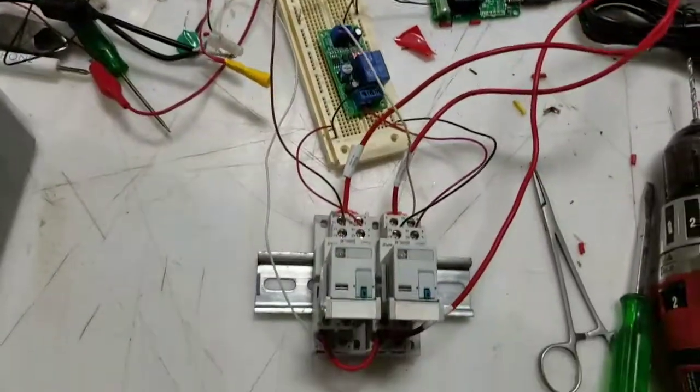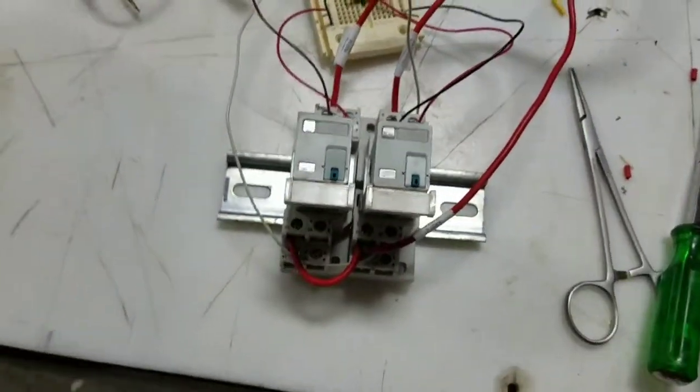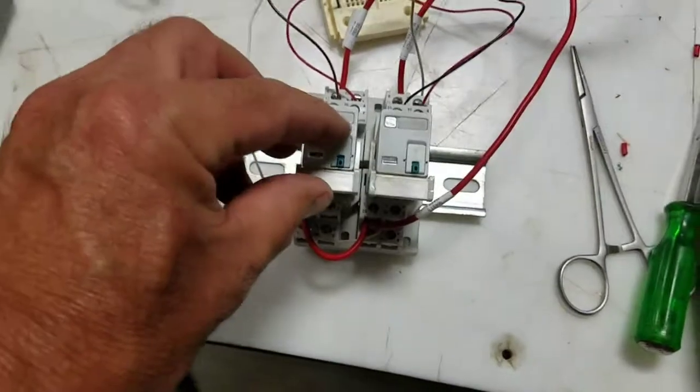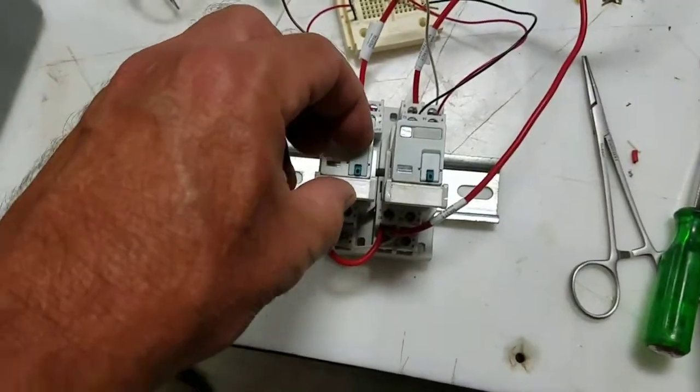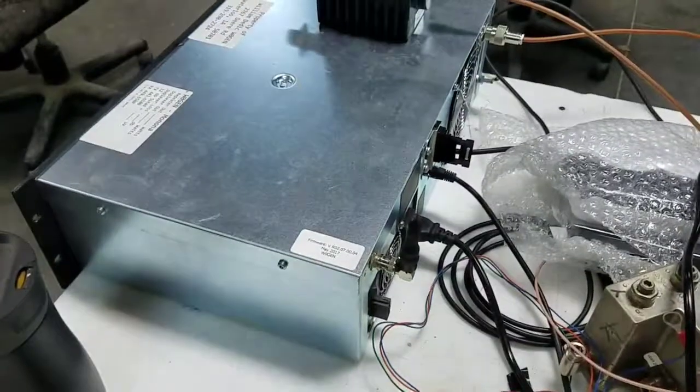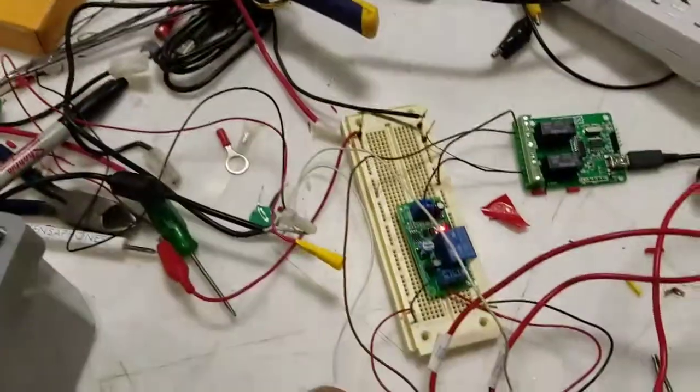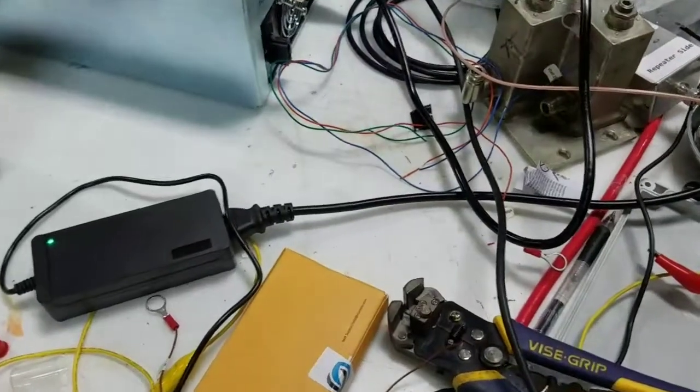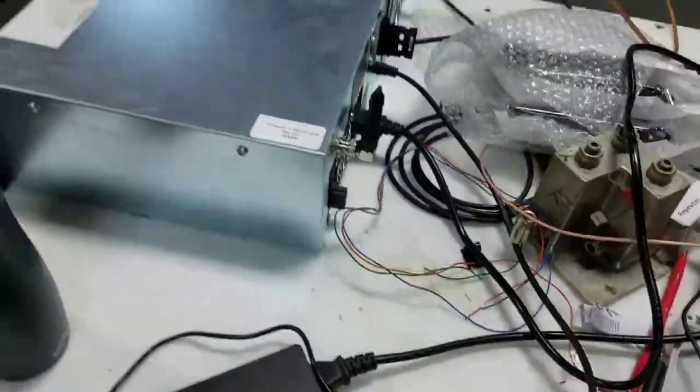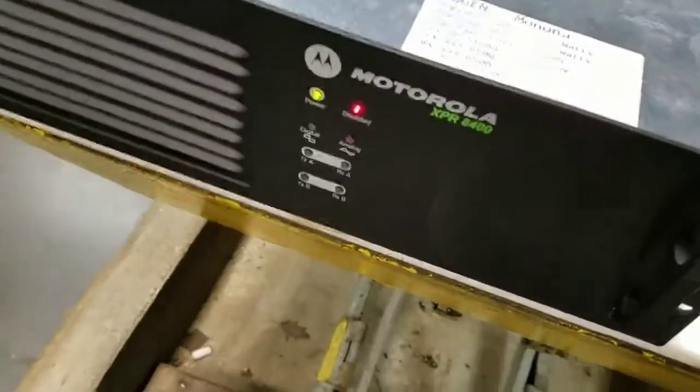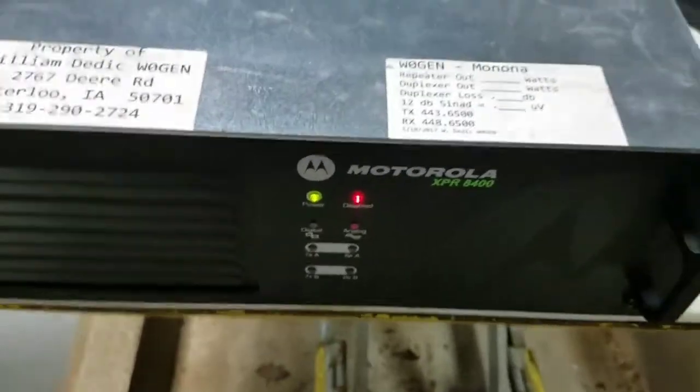And to test, if I manually override this relay, the repeater shut down. It's no longer running. I'll manually take control back on. Now the repeater is starting back up. So we have a successful test on that.